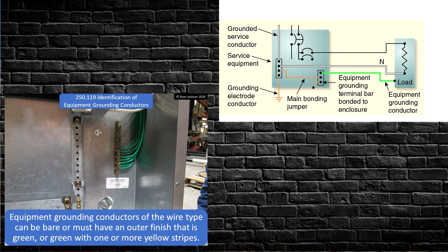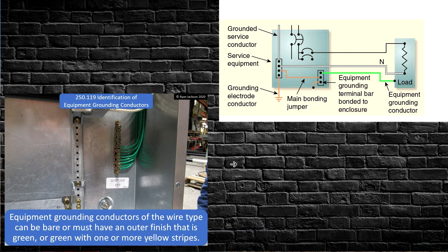Here are some examples. Per NEC 250.119, identification of equipment grounding conductors: EGCs of the wire type can be bare, or must have an outer finish that is green or green with one or more yellow stripes. An example diagram shows all three conductors together — the grounded service conductor (neutral), the equipment grounding terminal bar bonded to the enclosure, and the equipment grounding conductor.